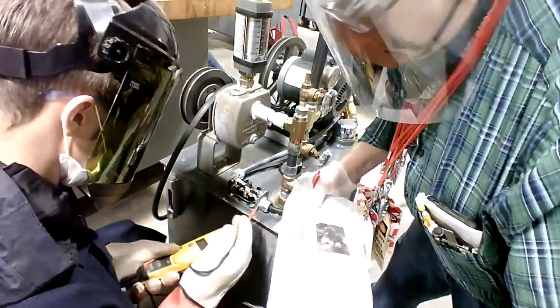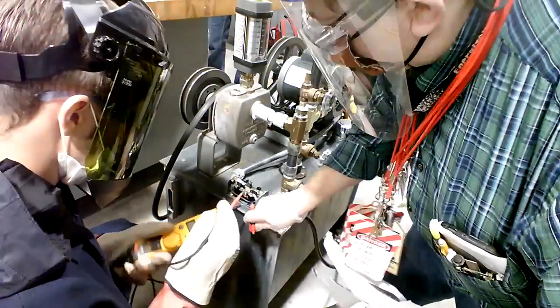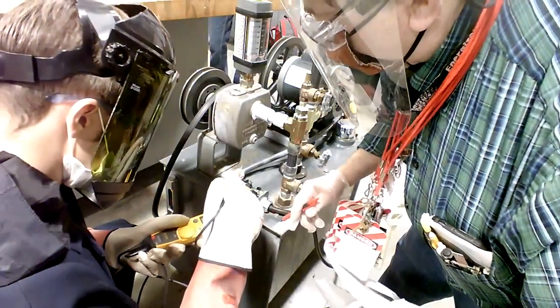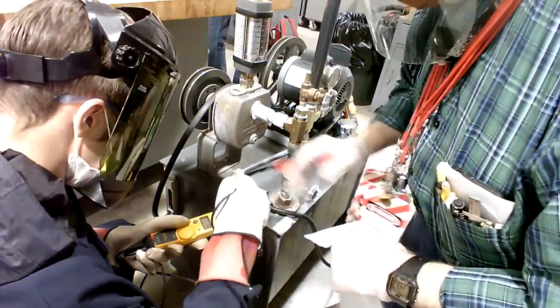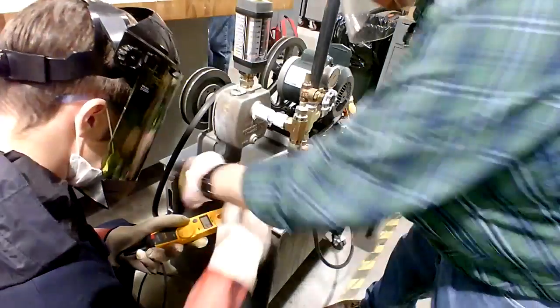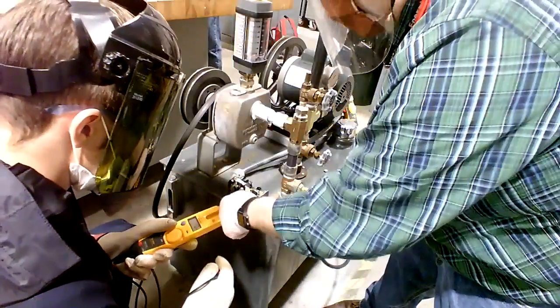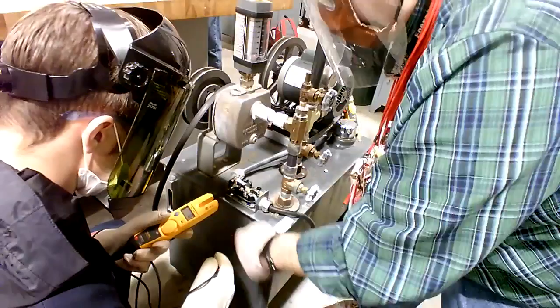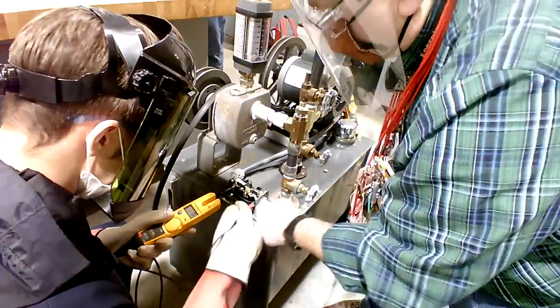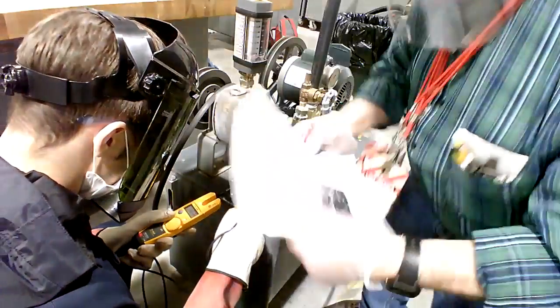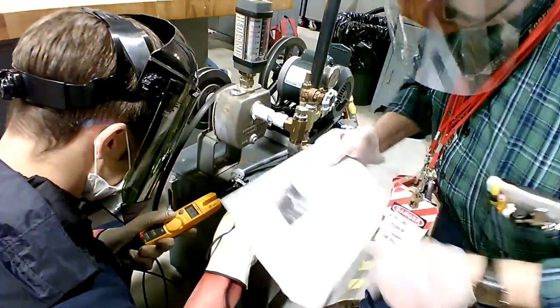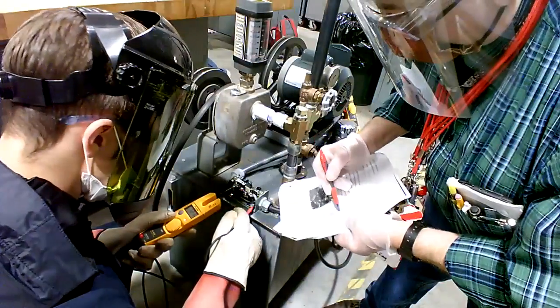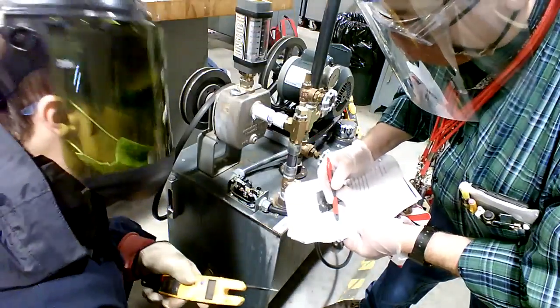And put one of your probes down here. You don't want to cross your hands over, so just reverse your hands. Actually, you can use that to check off, it's fine. The meter doesn't care on AC. Put the other plug on ground. You get the 121, right? But what you're doing, you're checking here. It stays hot. Now, what about here?